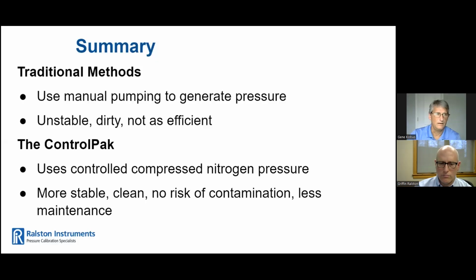So in summary, while the traditional methods of calibrating transmitters are effective, there are a lot of variables that can lead to unstable pressure, which affects test accuracy. Plus, you have to deal with priming, pumping, and all the steps involved in keeping a pump maintained and contaminants out. There are a lot of advantages of using nitrogen pressure control instead.